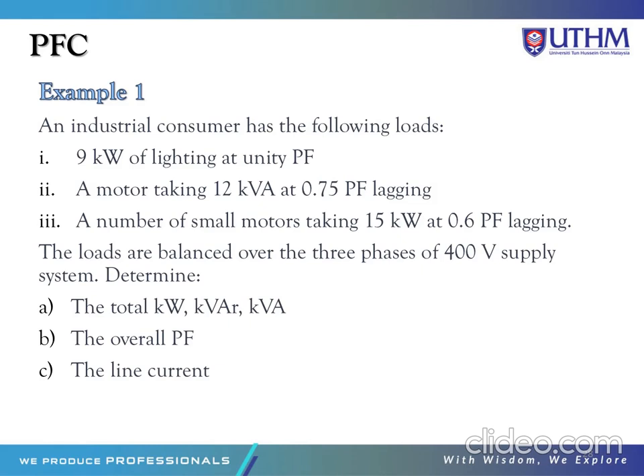So for PFC, we go to example 1. An industrial consumer has the following loads. Number 1, 9 kilowatt of lighting at unity power factor, and unity power factor is equal to 1. Then a motor taking 12 kVA at 0.75 power factor lagging. And a number of small motors taking 15 kilowatt at 0.6 power factor lagging. The loads are balanced over the three phases of a 400 volt supply system. The question is: A, determine the total kilowatt, kVAR and kVA for all loads; B, the overall power factor; and C, the line current.